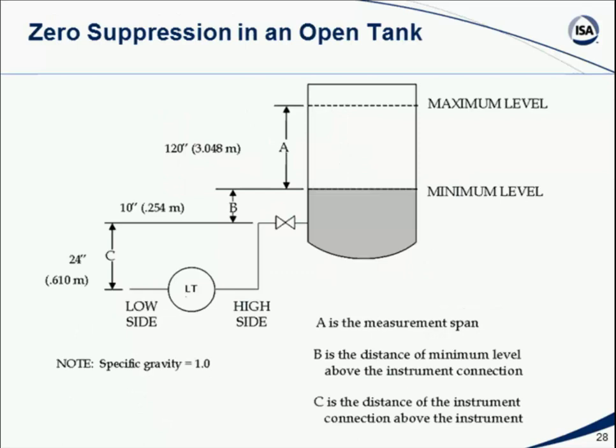We also have to correct for something else. When we talk about a column of fluid, we're not just talking about the fluid in the tank. Let's say my pressure measurement device is not mounted right there on the tank itself. I'm going to put my differential pressure sensor 50 feet away from the tank, and I'm going to run a small pipe, an impulse line, from the tap-off at the bottom of the tank over to that pressure transmitter. And in this case, now we are showing both the left and right side, or the high and low side. So this level transmitter is really a differential pressure device, and it's looking at the pressure on the low side, which is atmospheric pressure, and the pressure on the high side, which is both atmospheric pressure and the pressure generated by the column of fluid in the tank, and it's feeling the difference. And we just said a minute ago that if we use this kind of scheme, we can ignore the atmospheric pressure because it balances out. So we're going to ignore it for the moment.